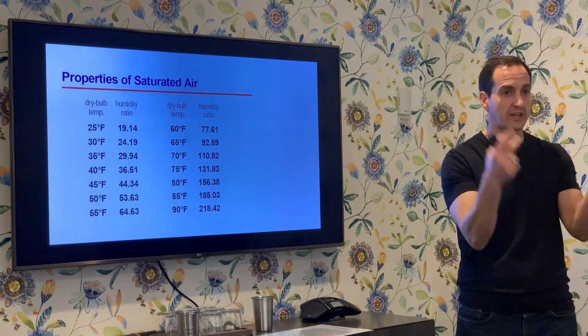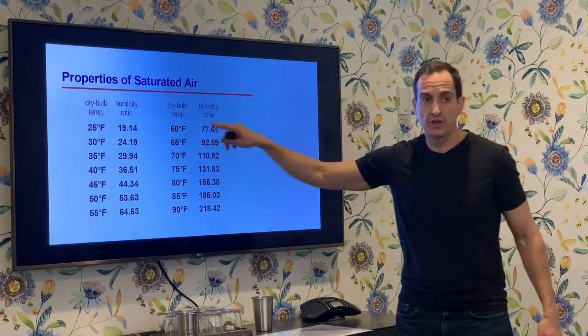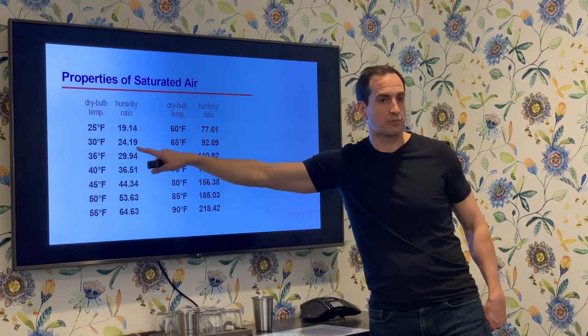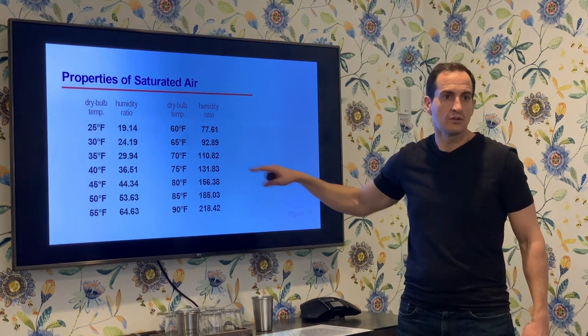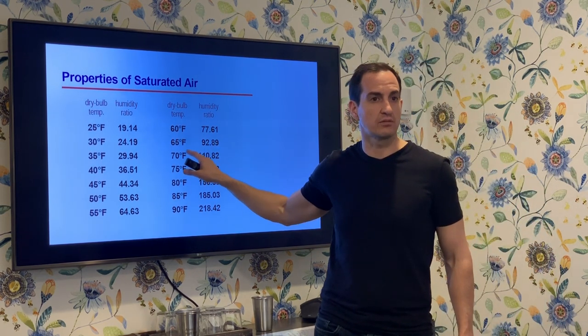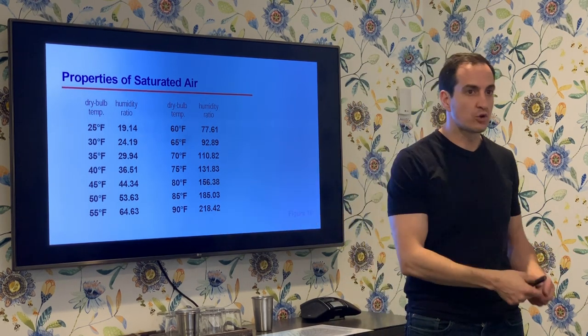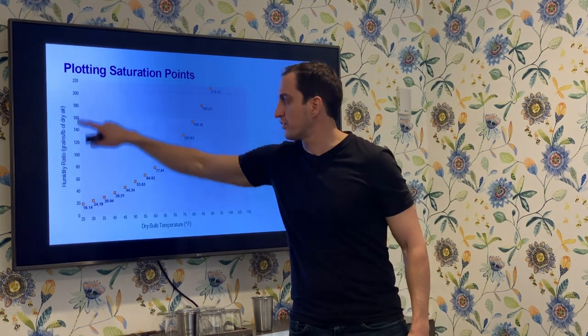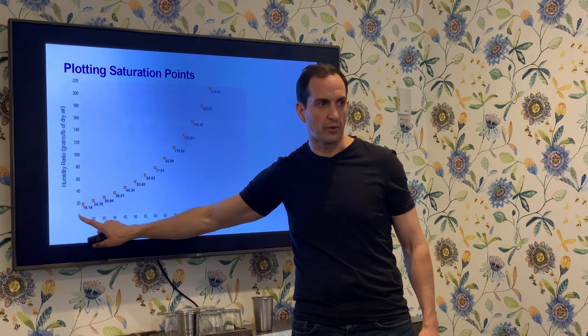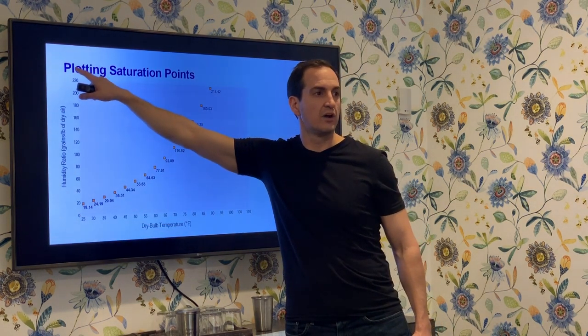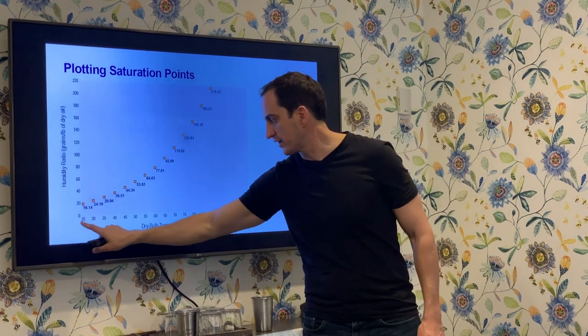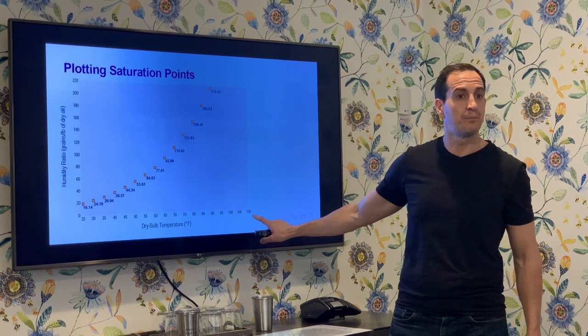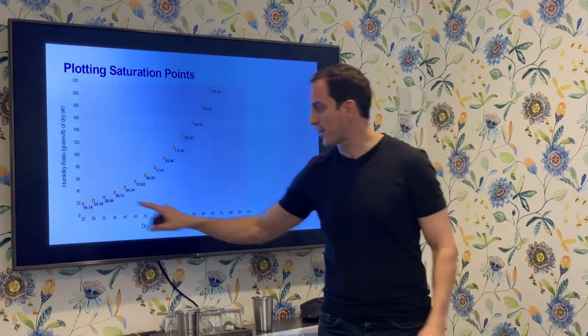At 55°F the grains per pound is higher, and as temperature goes up it doesn't increase by a constant amount — it becomes exponential. If we take these saturated points and put them on a chart with temperature in one direction and grains per pound of moisture on the y-axis, and plot the 100% saturated air conditions, they form a curve. This is our 100% relative humidity curve.